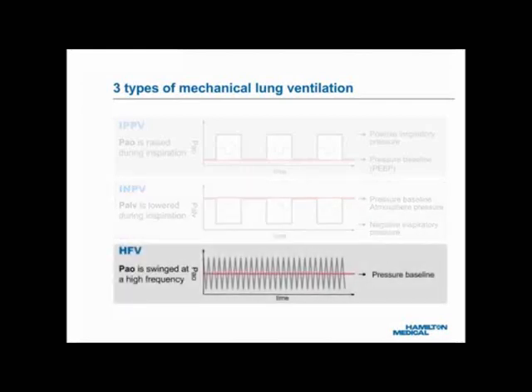Three: the bottom graph shows the pressure waveform of HFV, or High Frequency Ventilation. Using this principle, the airway opening pressure, PAO, is swung in a defined range around a defined pressure baseline, at a defined rate, which is at least 150 cycles per minute. Of the three principles, IPPV is the foundation of most modern ventilators, regardless of brand and model. From now on, whenever we say artificial lung ventilation or mechanical ventilation, we are referring to ventilation according to the principle of IPPV.